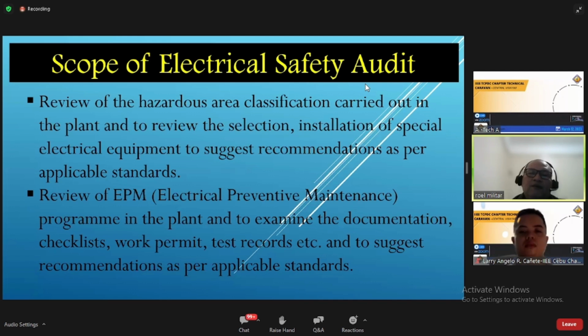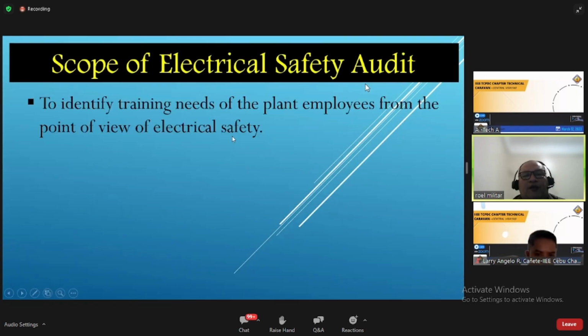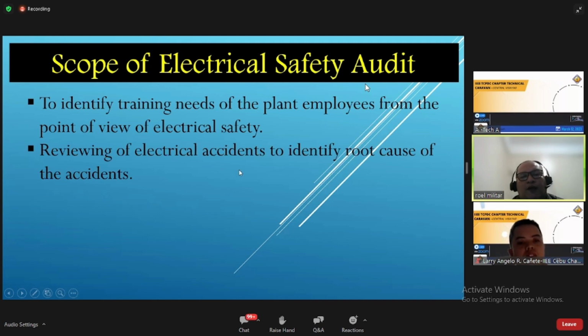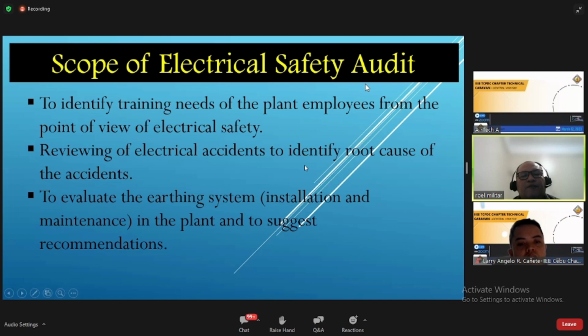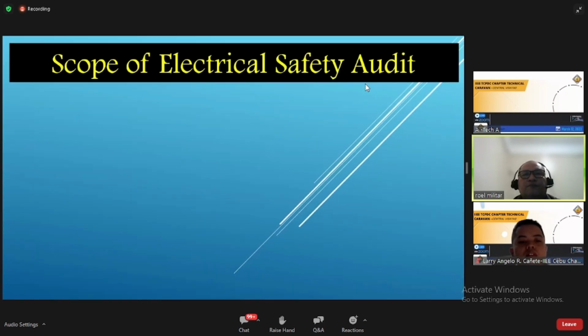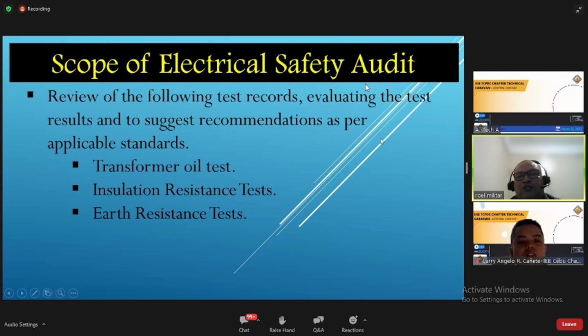So those testing results will also be reviewed when someone conducts this electrical safety audit. It will be reviewed also by the qualified personnel, to identify training needs of the plant employees from the point of view of electrical safety, to review electrical accidents, to identify the root cause of the accidents, and to evaluate the earthing system, the installation and maintenance in the plant, and to suggest some recommendations. It will review also the following test records, evaluating the test results and suggesting recommendations as per applicable standards: the transformer oil test, insulation resistance test, and the earth resistance test.